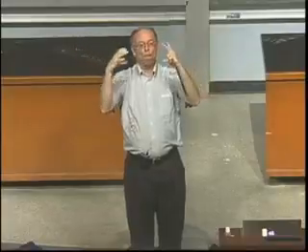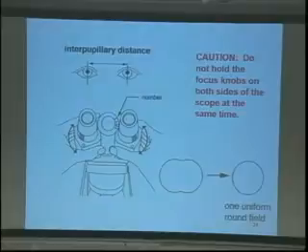If these two lenses are really far apart, you'll see two circles of light. As you push them closer together, you'll see them start to overlap. When they overlap, that's great, okay? And that's what this is trying to show you here, that image of pushing the oculars together, first far apart and then together, and you see the two fields of view overlap into one uniform field, okay? So that means you've positioned the interpupillary distance. You can write the number down.